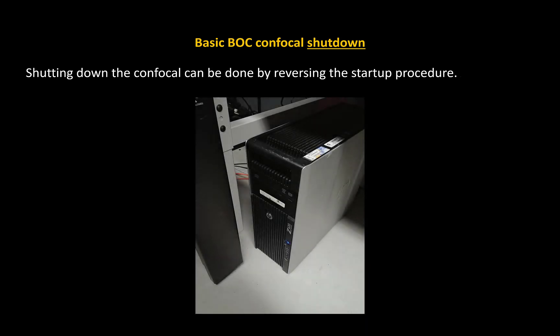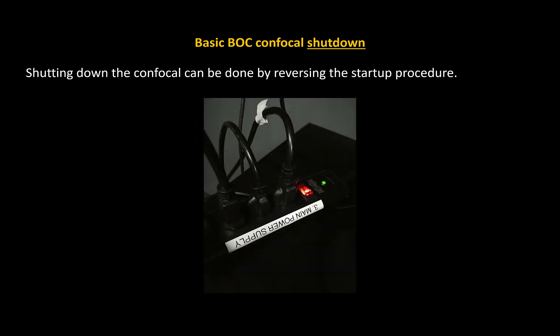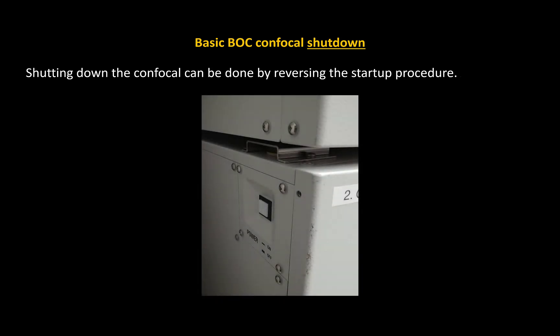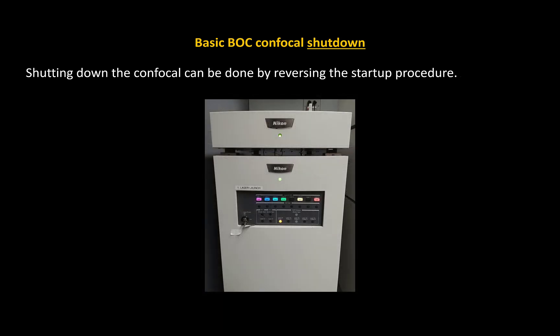Now the question is how do you shut down the confocal. Shutting down is the reverse of the startup procedure. First, shut down the computer after saving all your files. Then turn off the main power supply switch to turn off the microscope and LED light source. Finally, turn off the detectors and then the lasers.